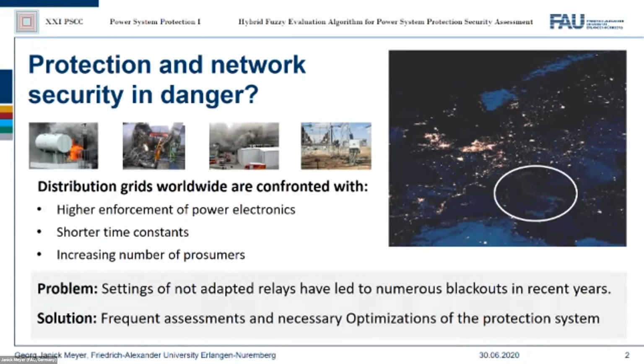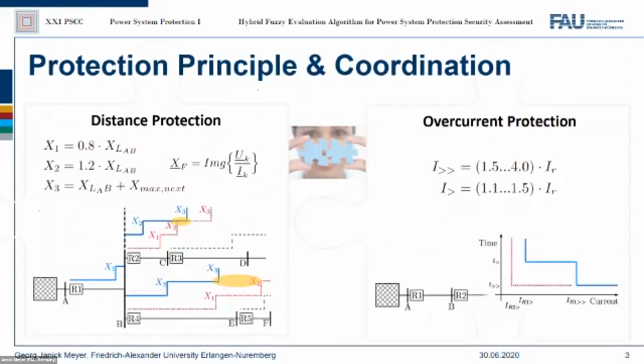An easy and effective solution to those events are frequent and quick assessments and necessary optimizations of the protection system coordination after major changes to ensure correct functionality. So let us take a closer look at the most common types of protection relays used in the distribution and also transmission grid with backup functionality, which are the distance and overcurrent protection.